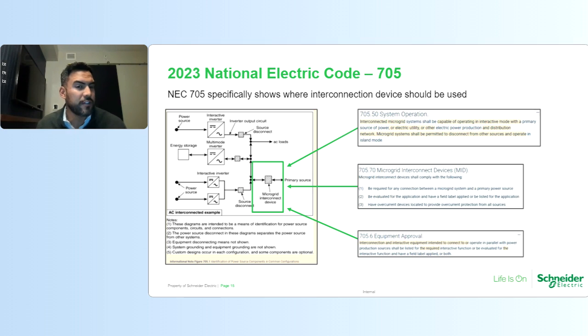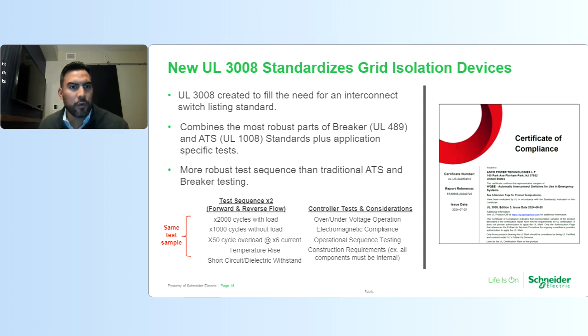A lot of this is relatively new technology, right? So it depends on the facility, the criticality, and if it's an emergency system legally required. If that's the case, you definitely want to look at SourcePack and the microgrid interconnection device to satisfy the UL listing requirement, to ensure that you're using the energy storage system correctly with the UL listed product. So we're going to go into the UL 3008 standard for grid isolation devices. This UL listing was created in partnership with UL to fulfill the need for the deployment of these energy storage systems. It combines the robust parts of the UL 489 breaker listing and the UL 1008 listing for transfer switches. And this automatic interconnection switch is put through rigorous mechanical testing.